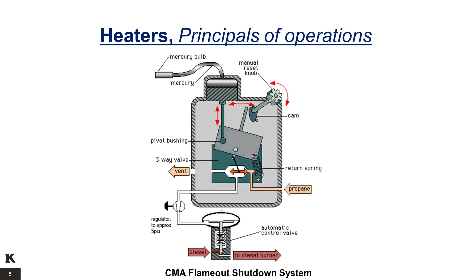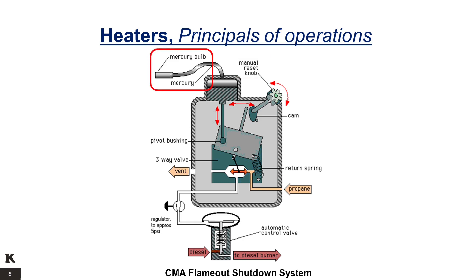The CMA flame-out shutdown system closes a pneumatic safety valve in the fuel line when the propane gas pilot light goes out. By turning the manual reset knob to the right, the gas inlet in the three-way valve opens, and gas passes to the safety valve servomotor and the pilot simultaneously. The safety valve opens and the pilot can be lit with the igniter. Once the pilot is alight, the mercury in the sensor and the capillary expands and pushes the stem down on the pivot bushing. This causes the orifice to remain open even when the manual reset knob is released. If the pilot flame goes out, the mercury in the capillary tubing cools down, the stem retracts and the return spring causes the valve handle to move, closing the inlet. As the safety valve servomotor is no longer supplied with gas, the valve closes by means of its return spring. Consequently, there is no danger of fuel being supplied to the main burner when the pilot is not alight.